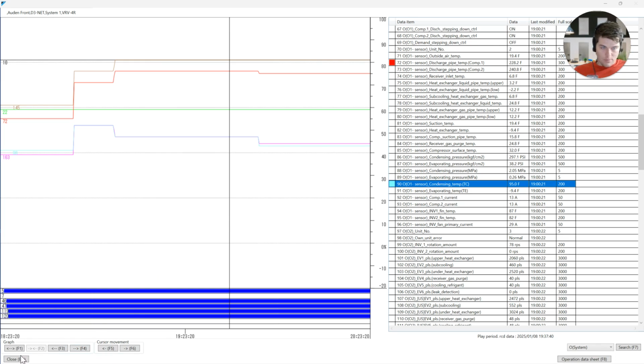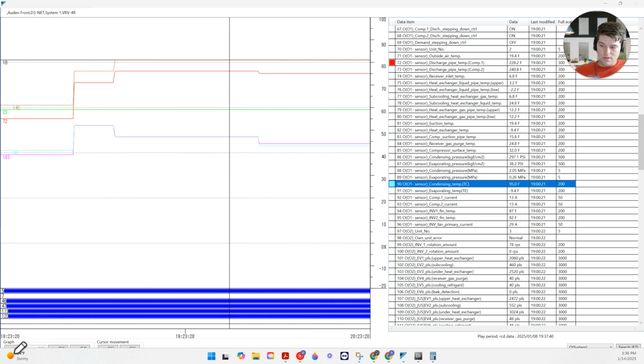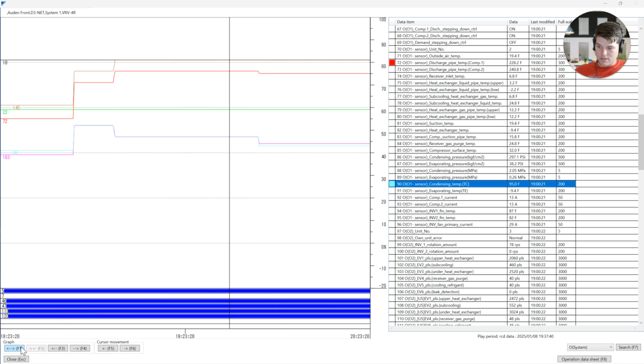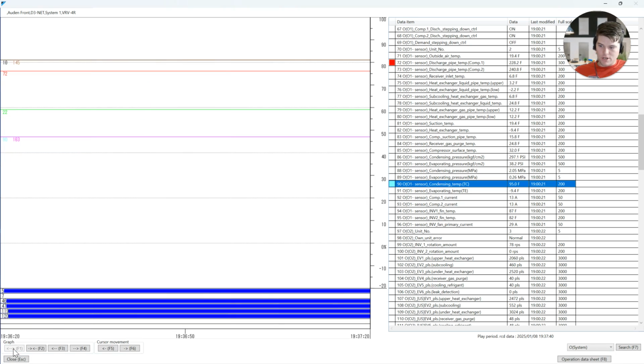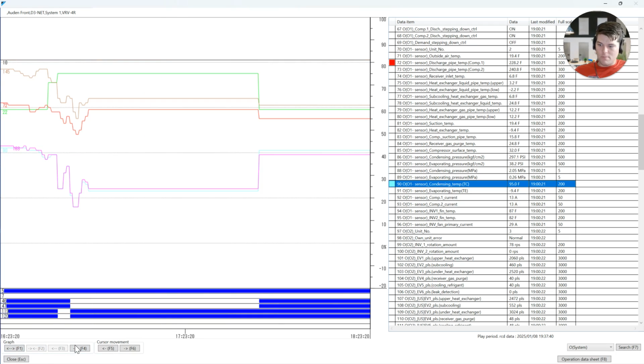How do you know 2 hours, Roman? Someone's out there asking that. 18:23:20, right? This is hour, minute, second. We are looking at a 2-hour timestamp from here all the way to over here. And again, if I zoom in, those timestamps are going to get different, which is this button here, F1. See how that number changes now? Now I'm looking at a 1 minute window. If you got guys who are troubleshooting a 1 minute window, you should be teaching me probably.